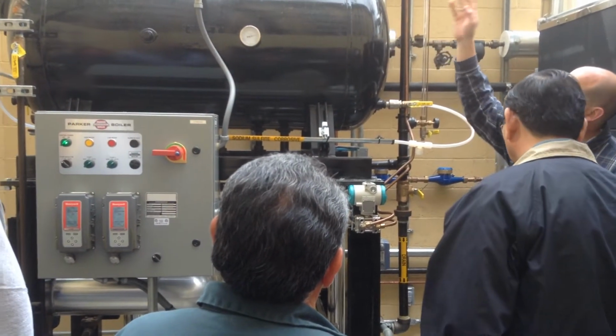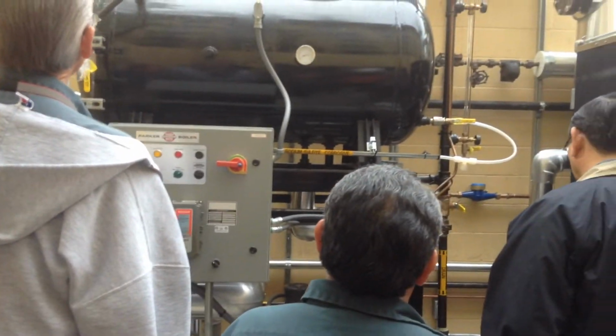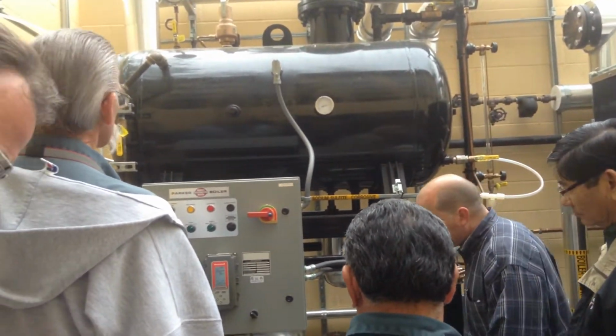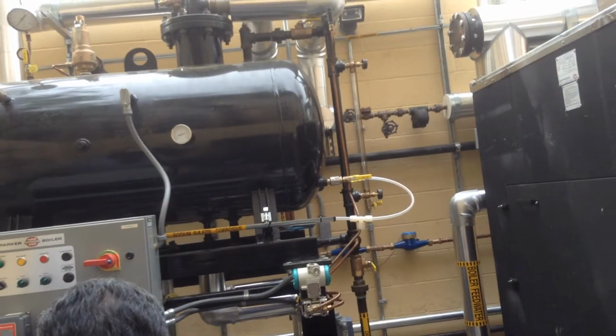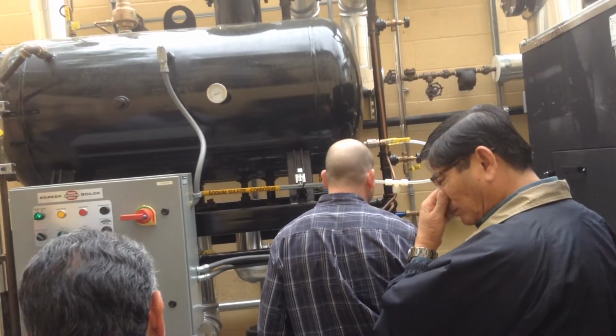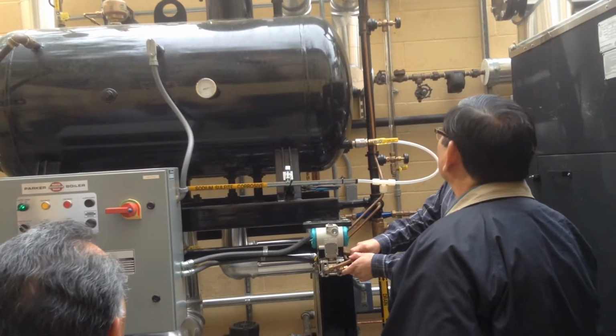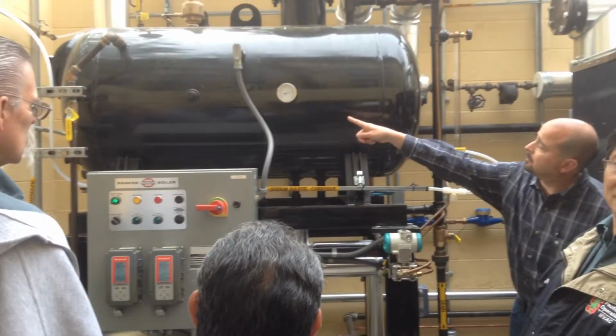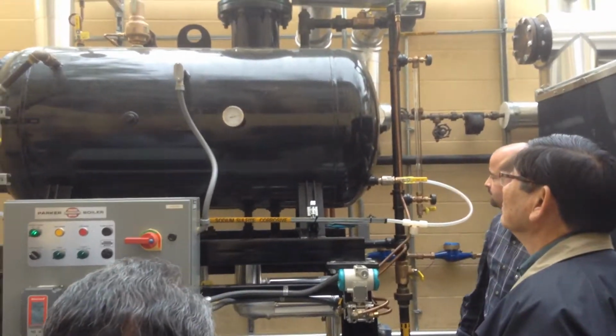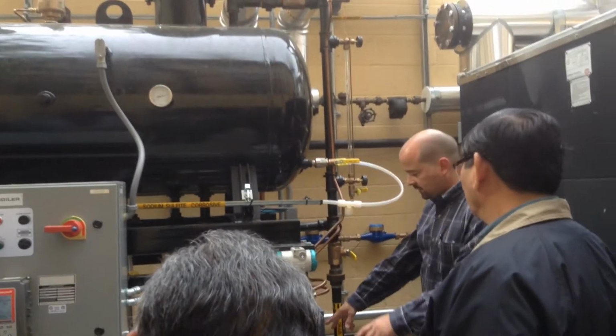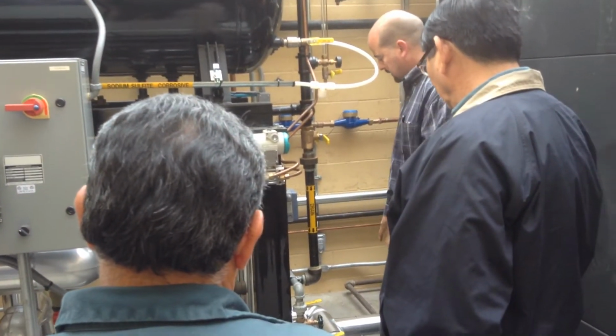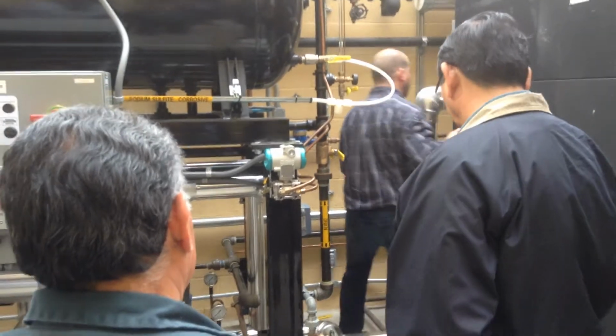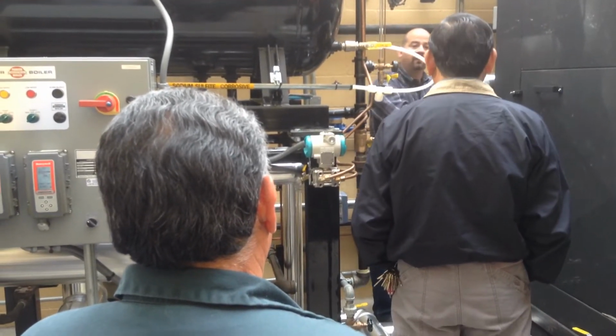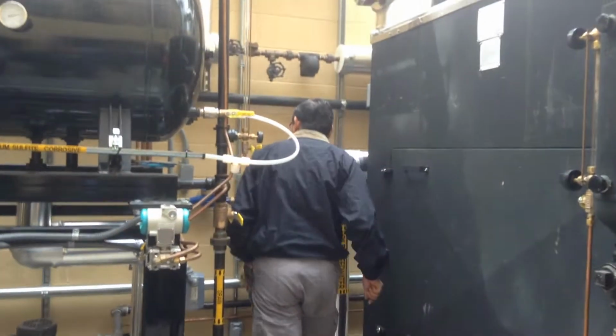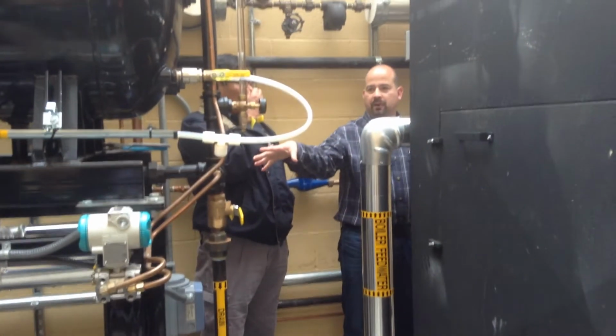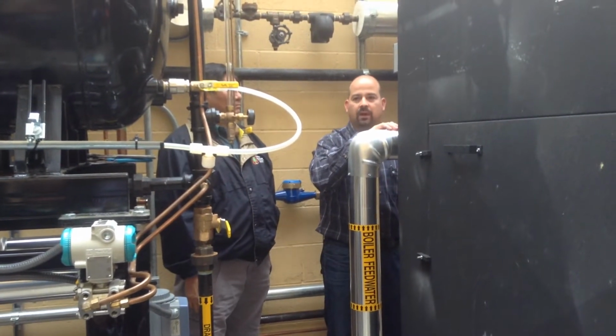So you've got your temperature gauge, you've got your safety relief valve. There should be an overflow trap right down here, steam trap. You've got isolation valves everywhere, obviously. You've got another bimetal thermometer here and your pressure gauge there. And then what happens is you have a common feed line off the discharge of the pumps, and it goes to the boiler in the back here. You can't really see it, but it really is just going in. There's a solenoid valve that's 120 volts. So whenever the boiler's calling for water, not only will it energize the pump, but it'll also open up the solenoid valve to allow water to go in.